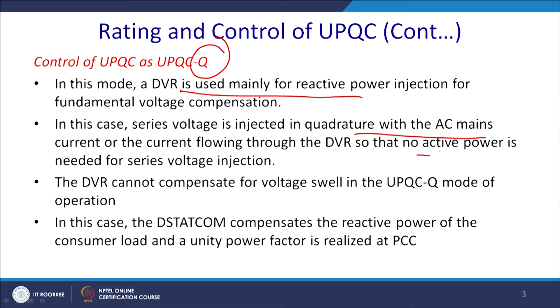So let us concentrate on the UPQC as UPQC-Q. It will inject voltage in quadrature. In this mode, the DVR is used mainly for reactive power injection for the fundamental voltage compensation. In this case, the series voltage is injected in quadrature with the AC mains current, or the current flowing through the DVR, so that no active power is needed for the series injection. It will not take any active power, only to meet the losses of the switches it requires active power.